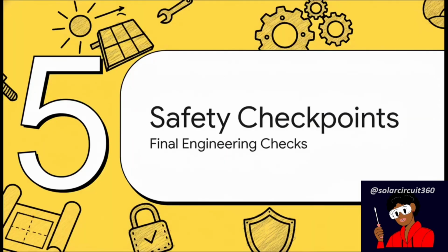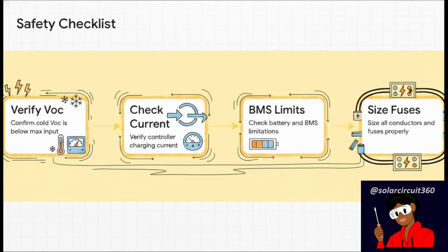Finally, we arrive at Section 5, Crucial Safety Checkpoints. Our source provides this definitive 4-step checklist to ensure total operational safety. Step 1. Verify that your cold weather Voc remains well below the controller's maximum limits. Step 2. Verify the controller's charging current can actually handle the load. Step 3. Check that your battery and your BMS can safely absorb all that incoming charging current. And Step 4. Properly size every single conductor and fuse to protect against faults. If all 4 of these checks pass, you're good to go.